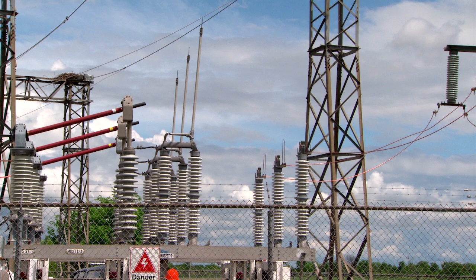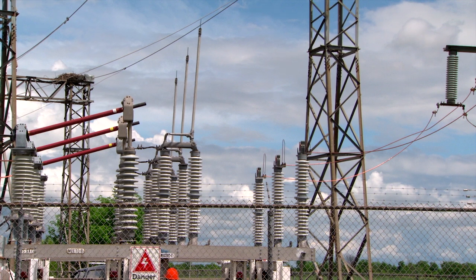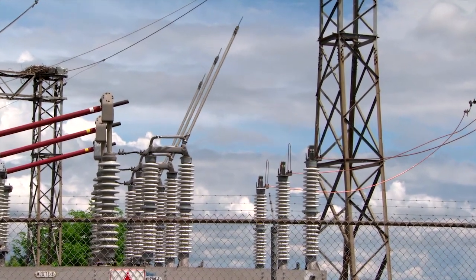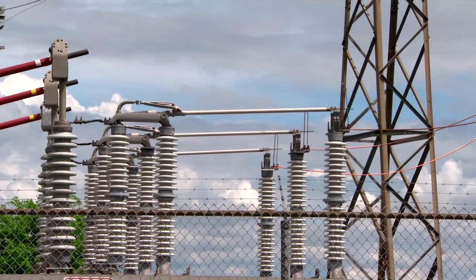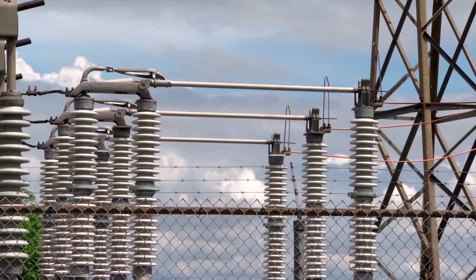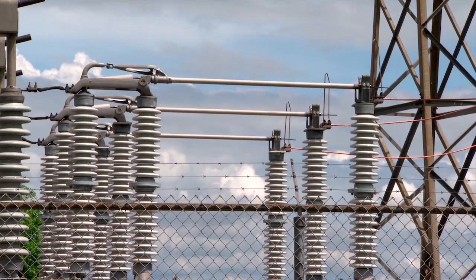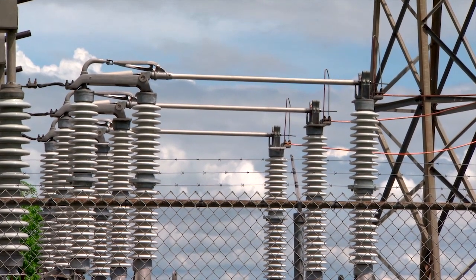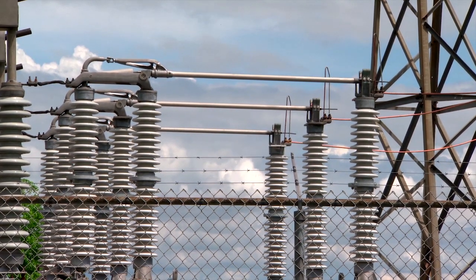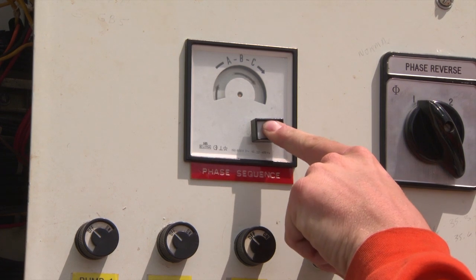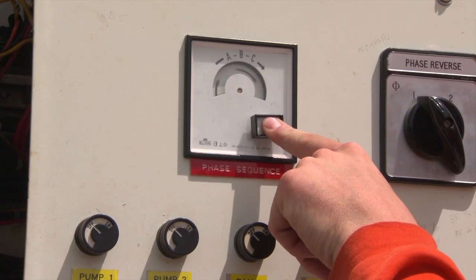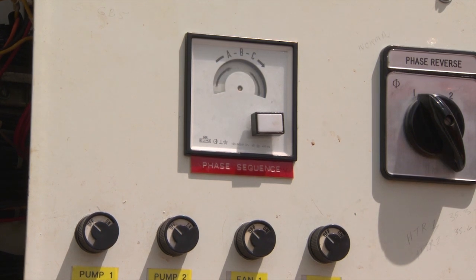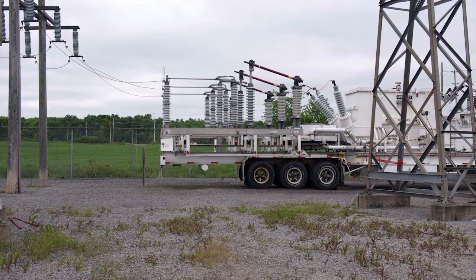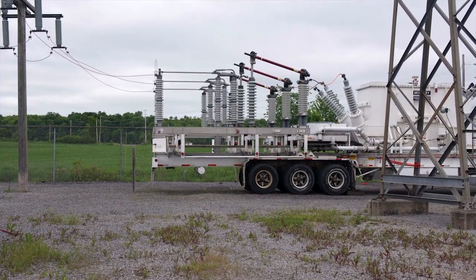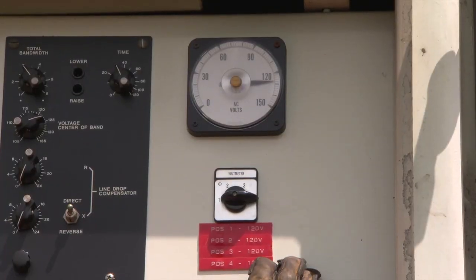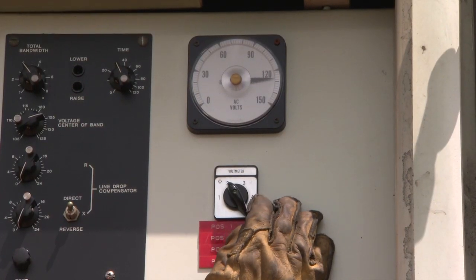Check that the MUS primary disconnect switch is open and remove the work protection tag. Wearing rubber gloves and standing on the grounding mat, close the high voltage switch. Check that all 3 phases are closed and turned in, and lock the handle in the closed position. The MUS is now on potential. Check the MUS phasing switch for proper rotation using the phase rotation meter located inside the transformer operating mech box. If the phasing is incorrect, you must take the MUS off potential and adjust as required. Check for 120 volts on all 4 positions of the MUS voltage selector switch.